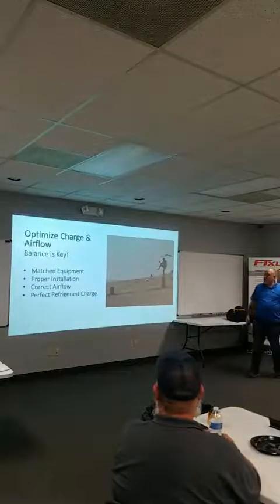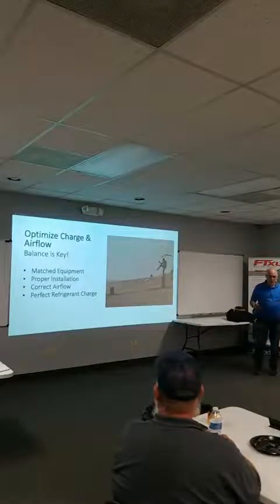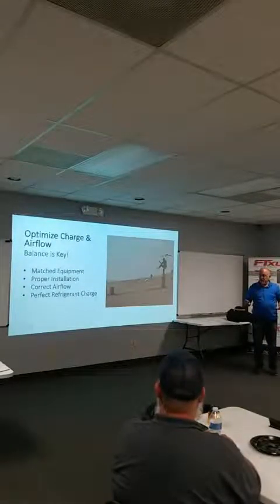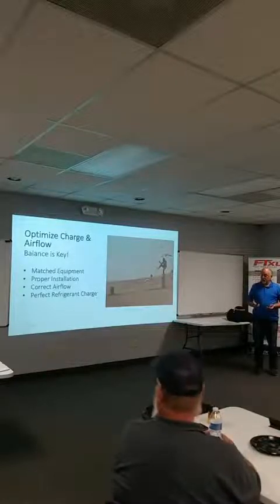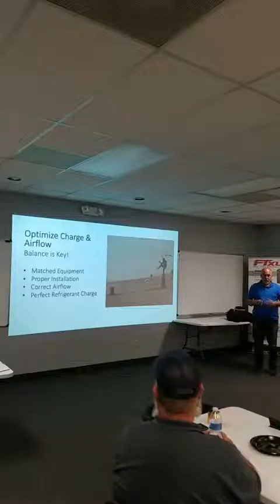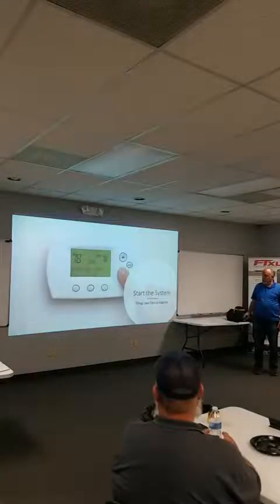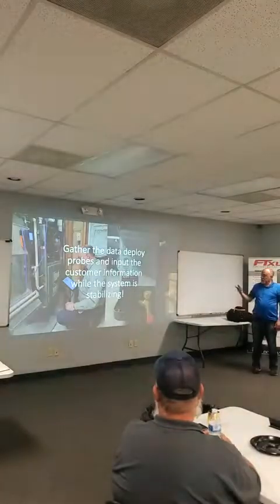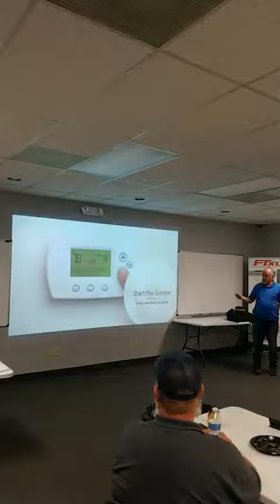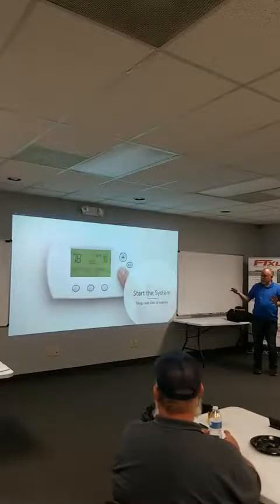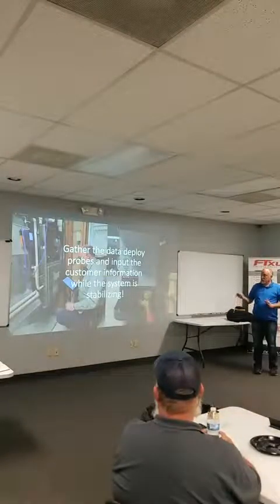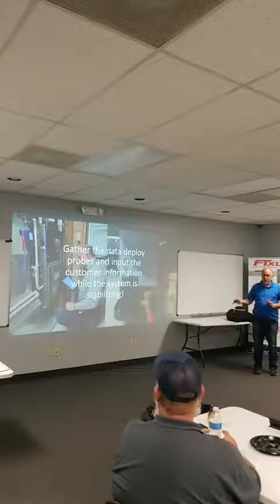Let's talk about optimizing. Once we've done our visual inspection and made sure everything looks right, the whole key to getting efficiency and capacity out of a machine is the balance of airflow and charge. Right? You've got to have correct airflow, you've got to have correct charge, or it's not gonna work. Okay? So we're gonna start the system up. At this point with Measurequick, we've done our visual inspection, everything looks good. We're gonna turn the system on, start deploying probes, and start gathering customer information about the system while it's stabilizing.